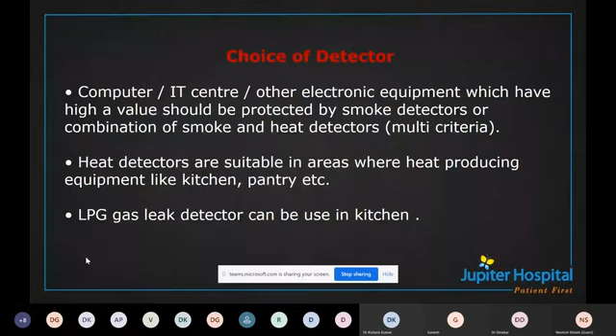Then along with the detector, there are types of detector. Normally we say analog detector, then digital detector, as well as an intelligent detector. So what is the meaning of that? An analog detector is something which has a fixed threshold. It's been given there. So the analog detector will give that signal to the panel. But then the fire alarm panel is a decision maker. In that case, the fire alarm panel decides whether we have to give the output device that signal or not, or whether we have to just consider it a false signal. So that depends on the panel and not on the analog detector. The analog detector just passes its signal on to the panel, and the panel becomes the decision maker.